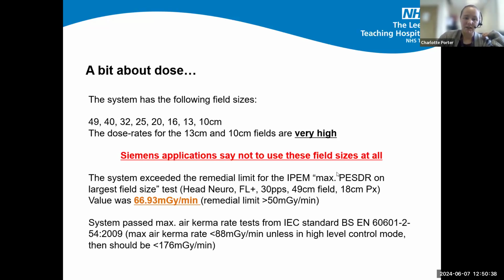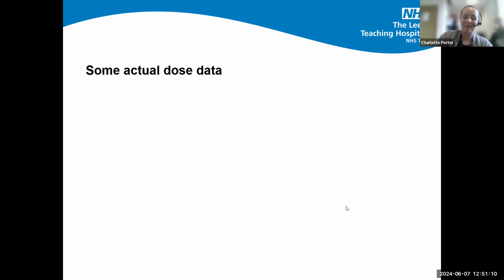We then did the testing to assess whether the system was compliant with the IEC standard with respect to the maximum air kerma rates, and it did pass those tests. I've not repeated this test. We've not quite got around to the annual QA for it yet. I would anticipate that since we've dropped that IQ level, we may find that it is no longer exceeding the remedial limit. But essentially, the system is capable of delivering some pretty high dose rates, so it's worth optimizing and worth keeping an eye on it.